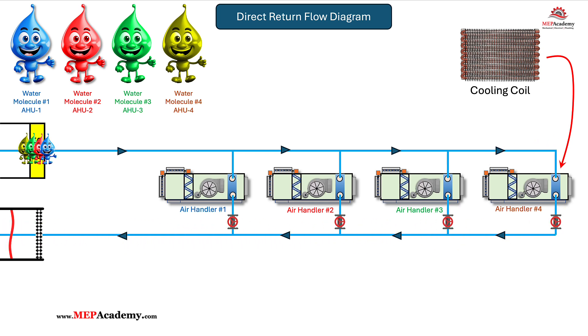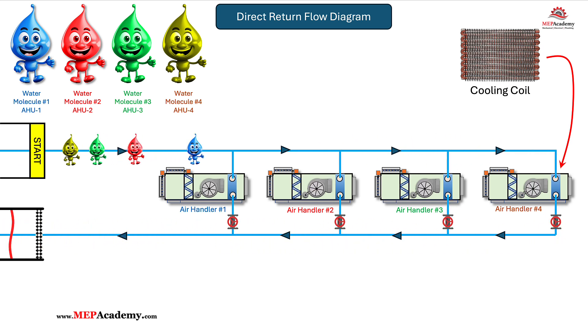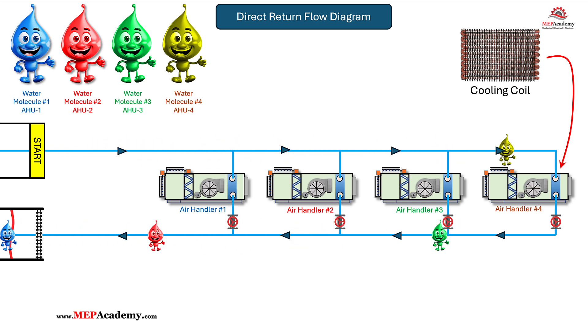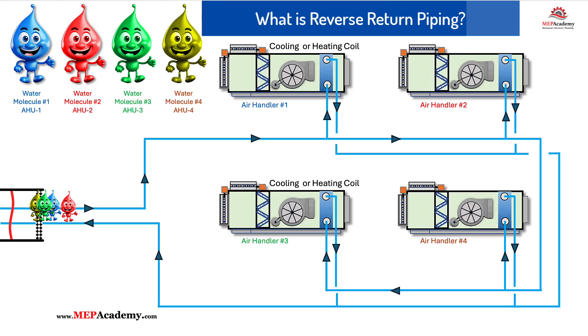If the pump is cycled on and water flows through the system, the water molecules leaving the chiller at the same time will reach each air handler coil at different times. If you must run 50 feet and your competition must run 100 feet, you will easily return to the finish line first. The closest coils will get fed first, while the farthest coil will receive chilled or heated water last.